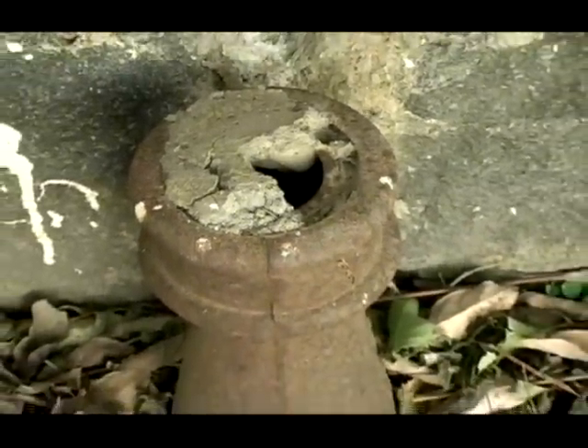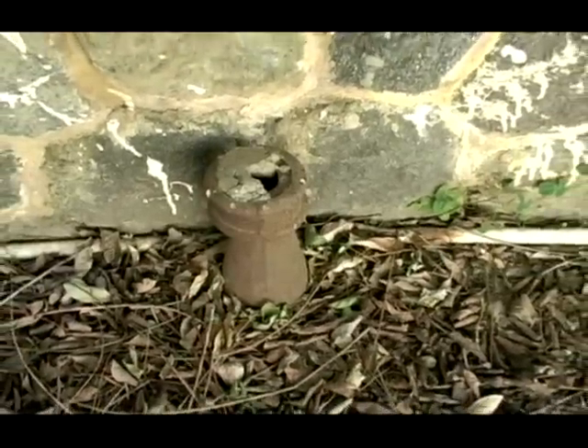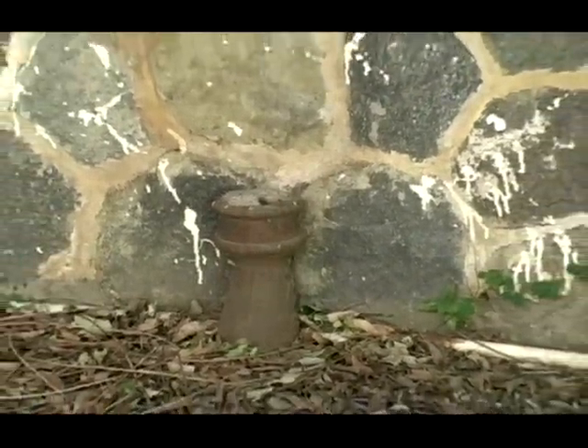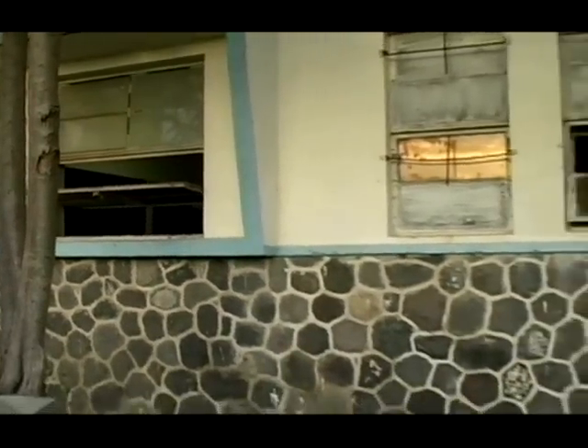All of this is obsolete — this system is not up to building code. It was done in the same style as the sugar factory back in the 1940s and 1950s. These cast iron vents are the breathers for the septic system, but you can see how close they are to the windows, so any fumes coming out of those go straight into the windows and cause people to get sick, in very close proximity to the classrooms.